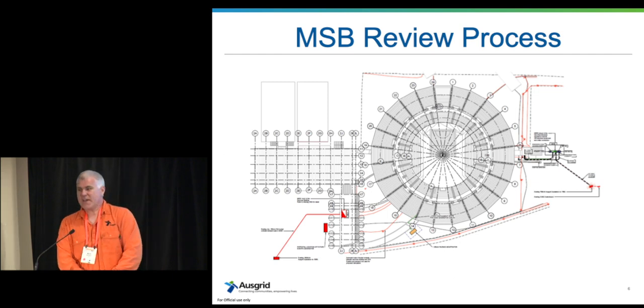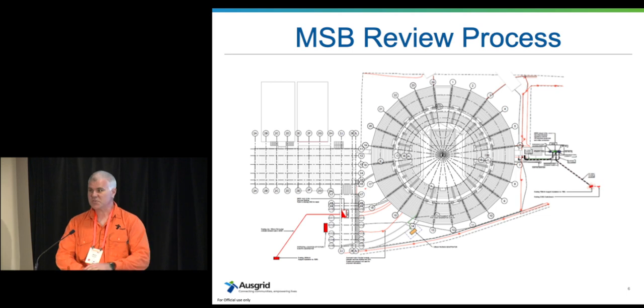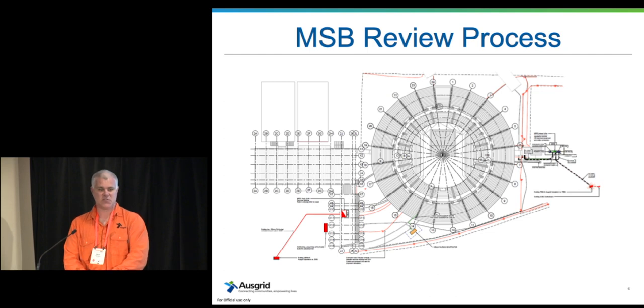Looking at the actual location of the switchboard, quite often we'll see a long set of consumer's mains or service mains coming into the building. On top of your Australian standards, on top of your New South Wales service installation rules, you've also got distributor requirements as well. So it's the same for any distributor. You need to make sure that you're quite savvy with those standards. So we've got Network Standard 112, which will talk about the length of those consumer's mains and how long they can or can't be.